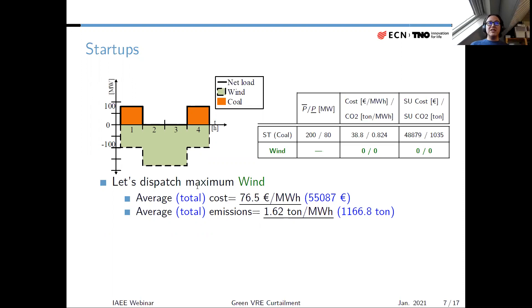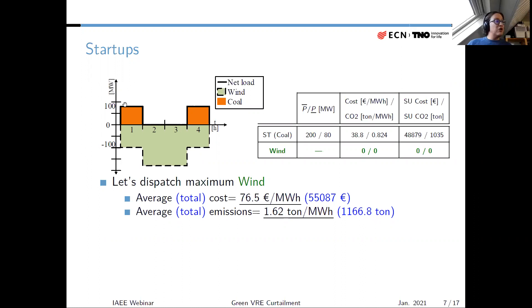These are the results if we dispatch wind at maximum capacity: the average cost and total cost are shown. Dispatching wind at the maximum possible, with the remainder covered by coal, gives an average cost of 76.5 euros per megawatt hour — almost twice the coal unit's cost of 38.8 — and average emissions of 1.62 tonnes per megawatt hour, almost twice the coal unit's 0.8.